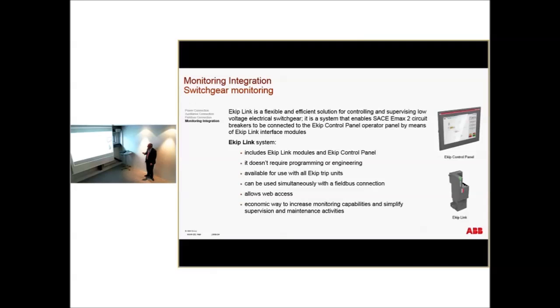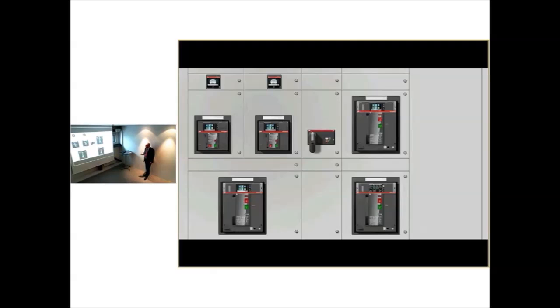This is the first, we are the first manufacturer to design this sort of device. I know some other ones are coming now, but this is an economic way to increase monitoring capabilities and simplify supervision and maintenance activities. There are some markets like oil and gas in the US, for instance, where you have a real arc-proof breaker, or you need to have the PPE, everything in order to be close to the breaker, or you need to operate the breaker in that way.